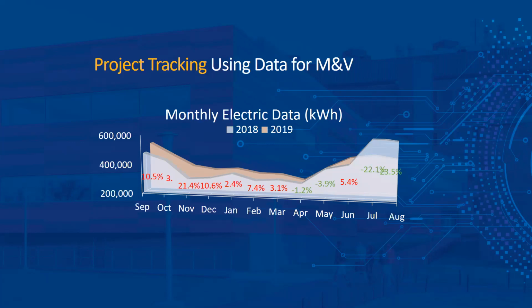Some of the other things we use it for outside of M&V: we baseline buildings, we could right size equipment, we can confirm the equipment is running properly, and catch maintenance issues. With COVID and all these buildings being unoccupied, we benchmarked baseline per square foot, and we can notice when buildings are a lot higher than they should be. One of the buildings we noticed had hot water valves that were passing, so it's a good conversation piece to go to our HVAC department, and they could schedule those to be fixed.